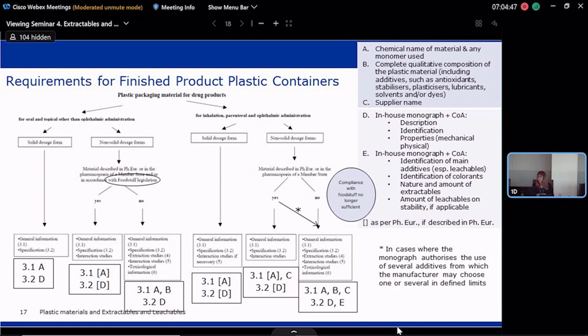And then you need to be aware that when there is compliance with the European Pharmacopoeia or a Pharmacopoeia of a member state, it's important to look at the monograph, because if the monograph authorizes the use of several additives from which the manufacturer might choose one or several, then compliance with the Pharmacopoeia is no longer sufficient. We need to have extraction studies and, if needed, toxicological information.